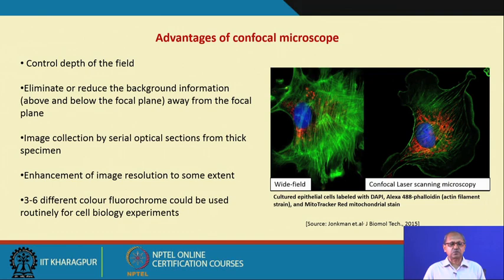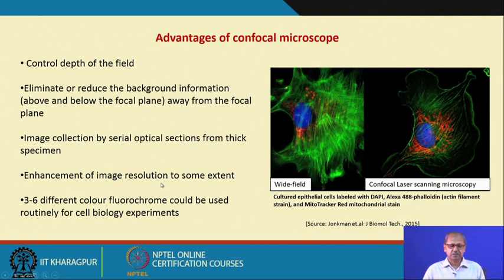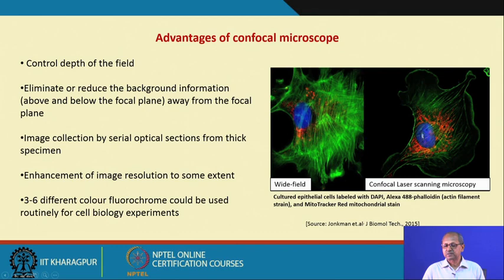In contrast, using confocal microscopy provides several advantages: control of depth of field, elimination or reduction of background information from above and below the focal plane, image collection by serial optical sectioning from thick specimens, and enhancement of image resolution due to the pinhole. Up to 3 to 6 different color fluorochromes can be used routinely. The same epithelial cell imaged with confocal microscopy gives very sharp images of the nucleus, mitochondria, and actin filaments.